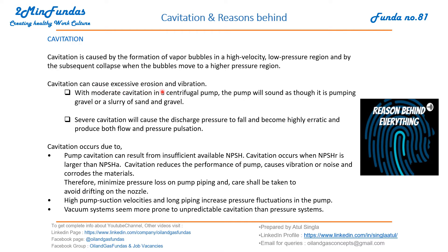Cavitation can cause excessive erosion and vibration. Once cavitation is present inside the system, it can cause erosion of the pipe and vibration of the system. With moderate cavitation, if a small amount of cavitation is there in a centrifugal pump, the pump will sound as though it is pumping gravel or a slurry of sand and gravel, creating unnecessary noise in the system.